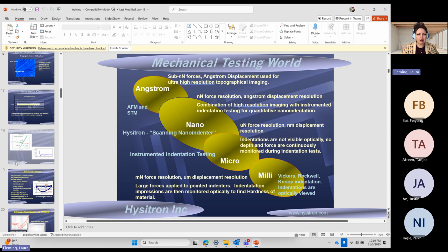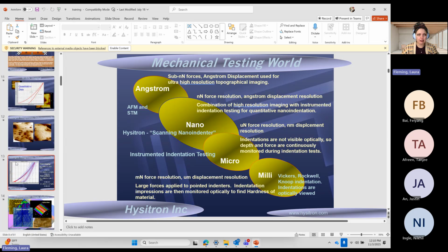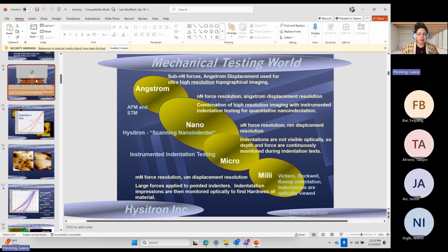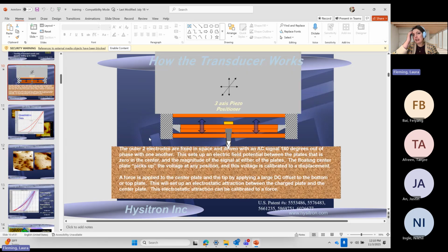So how do we actually get hardness and modulus information out of the transducer? What I would like to point out is that the transducer is a 3-plate capacitive transducer, meaning you have a top plate, a bottom plate, and a center plate. And the center plate is connected to the sidewalls by these teeny tiny springs. It's really important when we're talking about handling the transducer, because we have to make sure to keep those springs safe. If we bend those springs, the sensor is no longer functioning and there is no repair to be had.